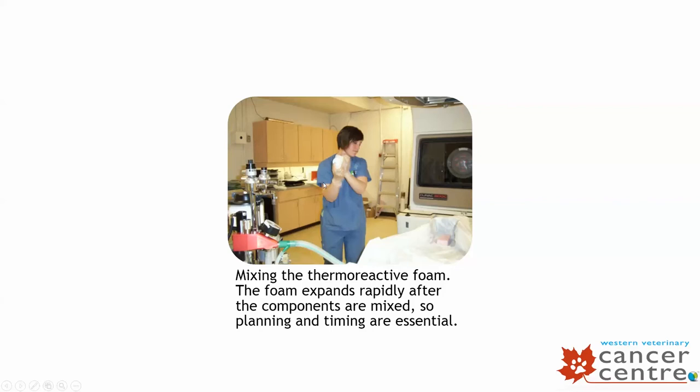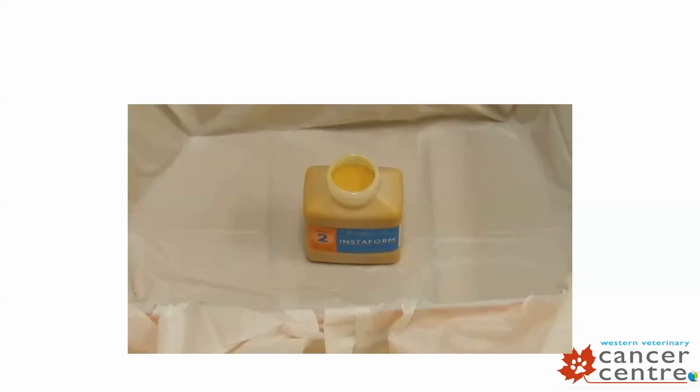Again, two separate compounds that you mix together. The instructions are to shake vigorously for 20 seconds. We learned the hard way that you need to stick to that 20 seconds early on in our stereotactic learning curve. Well, we got distracted while we were making up one of the bottles of foam, set it down to answer the phone, and that was followed by a pretty loud explosion a little later, and then many months of us scraping hardened foam off of pretty much every structure in the LINAC vault. So planning and timing is fairly essential when you start making up the bottom part of the immobilizer.